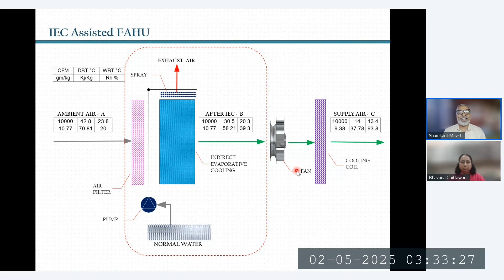Today we are designing these kinds of AHUs that take enough pressure, take return air, and have smart controls monitoring what's happening in the ambient and in the space. Accordingly, they decide whether to take only fresh air, return air, a combination, and so on. Systems are becoming smart enough, thanks to modern controls, that the AHU itself can decide—let's say if I'm in Pune with a 24x7 working office, when Pune ambient goes to 20 degrees, there's no reason I should be running my chiller.